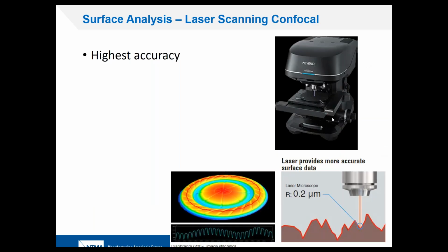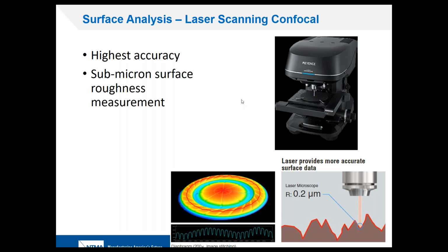All right. The next step up, tip of the spear, we'll say, in terms of accuracy or precision is laser scanning confocal technology. There are a few different manufacturers of those on the market now, but this is going to be if you're really trying to understand surface finish, surface roughness. This will use a high resolution laser to raster across the surface, and then generate a 3D image like you can see there in the bottom middle of your screen.